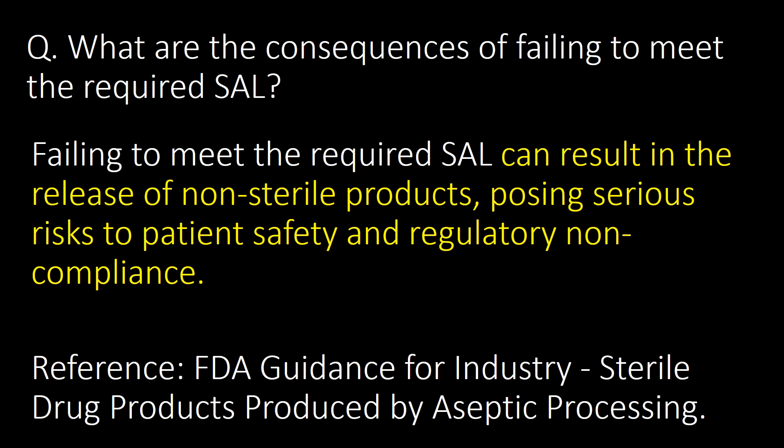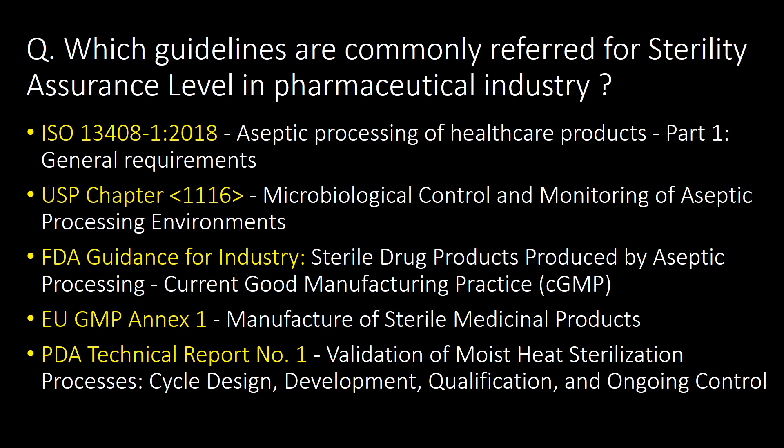What are the consequences of failing to meet the required sterility assurance level? Failing to meet the required SAL can result in the release of non-sterile products, posing serious risk to patient safety and regulatory non-compliance. Reference: FDA guidance for industry. Commonly referred guidelines for sterility assurance level include ISO 13408, USP Chapter 1116, FDA guidance for industry, EU GMP Annex 1, and PDA Technical Report No. 1.